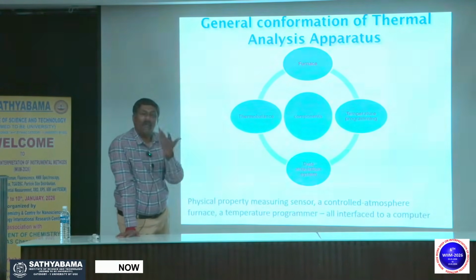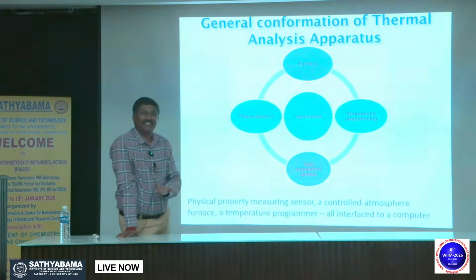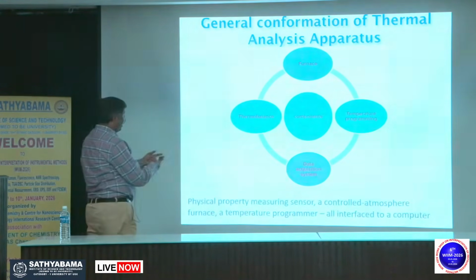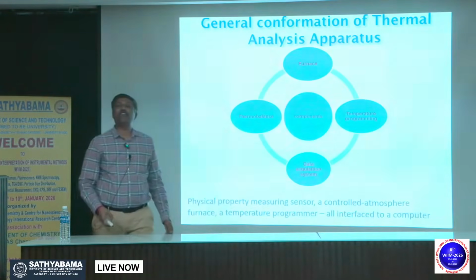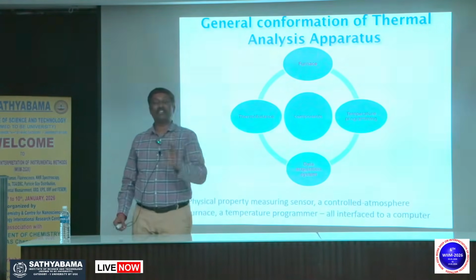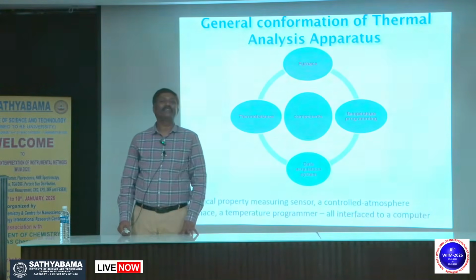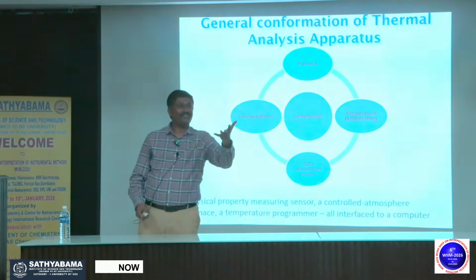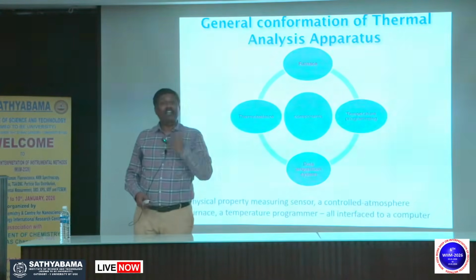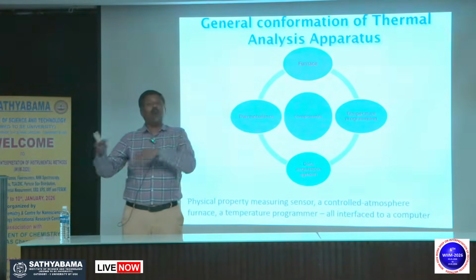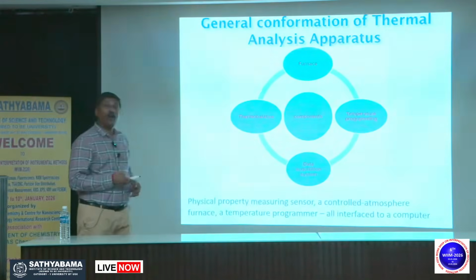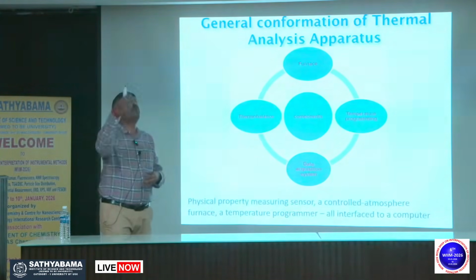Silver is a bit expensive, platinum is more expensive, quartz. And then your balance, you're working at 1500 degrees Celsius, the balance should behave the way it behaves at 50 degrees Celsius or 5 degrees Celsius. And that's where the challenges are. And that's where the cost of the instrument we are paying. Robustness. The interference of the temperature on the property should be as minimal as possible, or at least it should be predictable so we can do the correction.